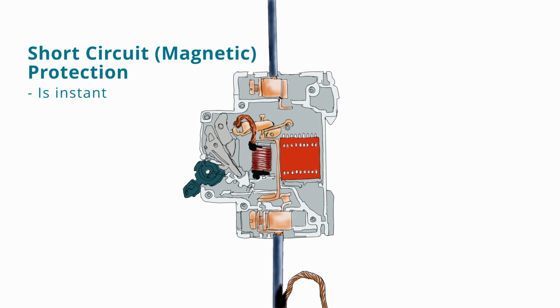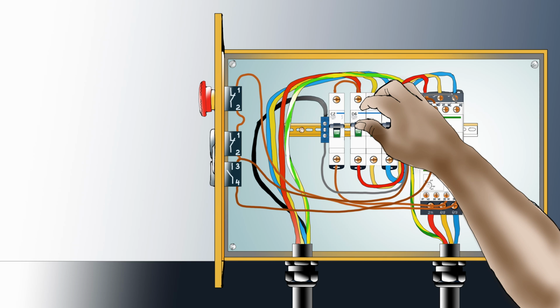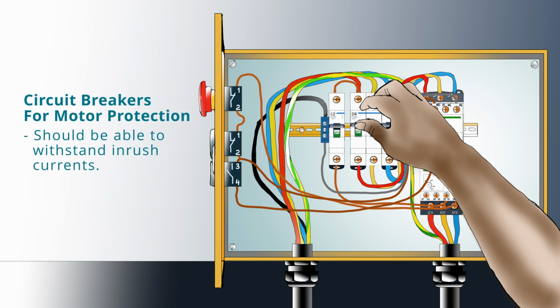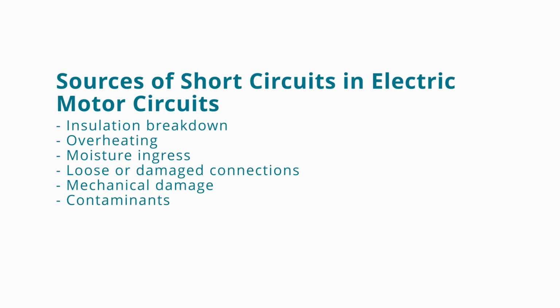The operation of a circuit breaker with regards to short circuit faults is instant. When selecting circuit breakers for motor protection, we select a type that protects our circuit against short circuits, whilst also withstanding the large startup currents without nuisance tripping. These are typically D-curve circuit breakers or C-curve circuit breakers for small motors. Now the following is a list of sources of short circuits in electric motor circuits: insulation breakdown, overheating, moisture ingress, loose or damaged connections, mechanical damage, or contaminants.